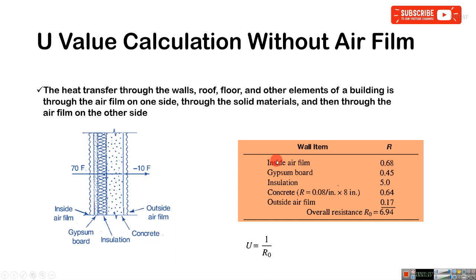Then inside air film R-value is 0.68. This is gypsum board R-value, insulation R-value, concrete R-value, 8-inch concrete, the outside film R-value. The overall resistance R0 equals 6.94. Then 1 divided by R0 gives you U-value.